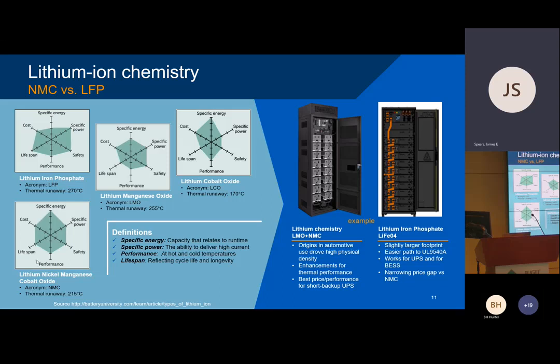Why? They want the most mileage per charge, and nickel manganese cobalt has excellent specific energy. If you look at the spider web charts on the left, NMC is in the lower left, and the specific energy line at the 12 o'clock position is quite high, with specific power pretty good too. What's the difference? Specific power is the battery's ability to dump all its energy relatively quickly, like in a UPS system with a 5 or 10 minute battery. Specific energy relates more to longer, slower discharge and how optimized the battery is for that application. Safety, at the 4 o'clock position, is quite good for NMC. Performance at the bottom means performance at temperature, lifespan, and cost.